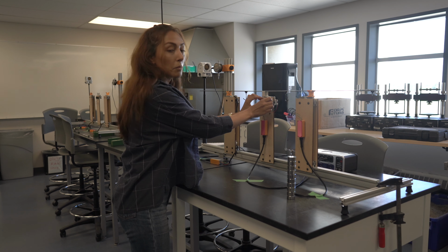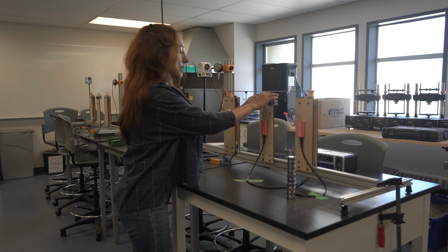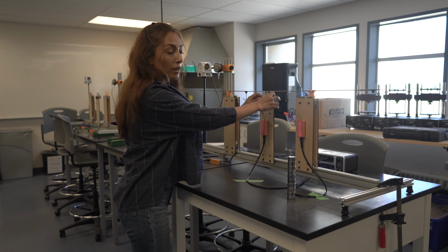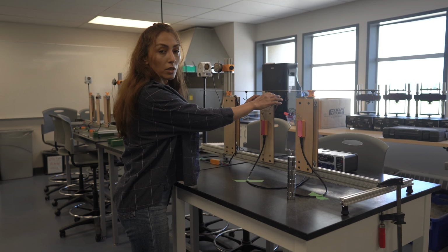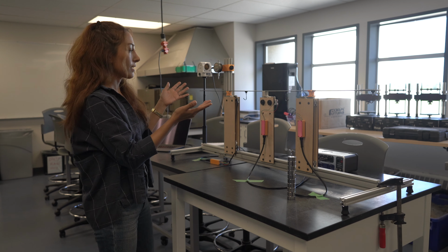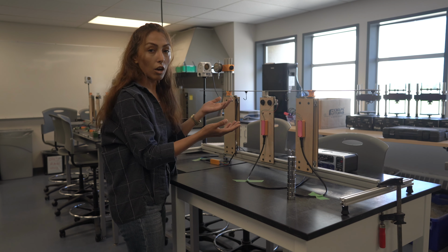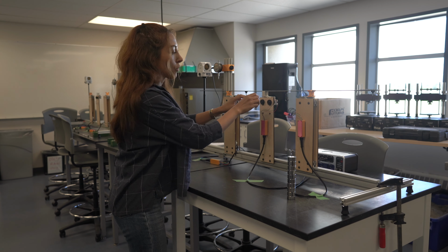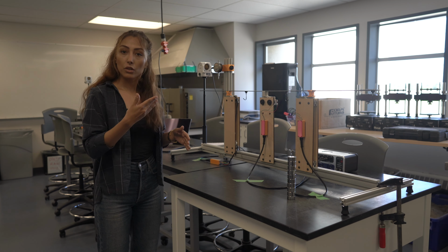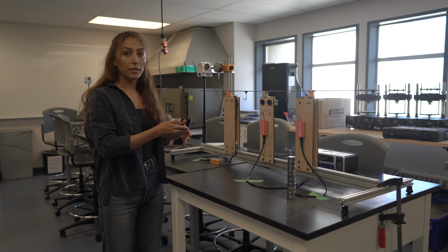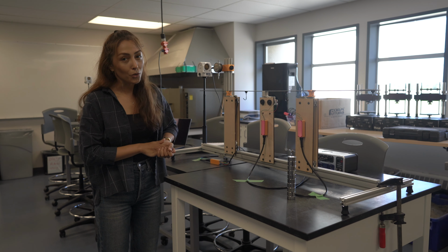When you loosen up these bolts, you can adjust the height of this middle support. Let it rest at its unstressed position, and then fix these. You perform this step in case previous groups left it under support settlement, so you loosen it up, but make sure you don't do that.